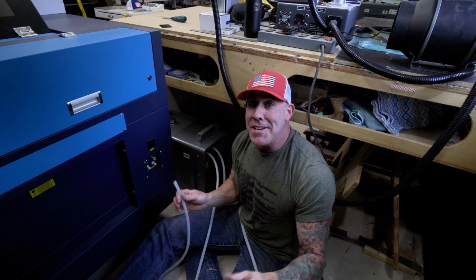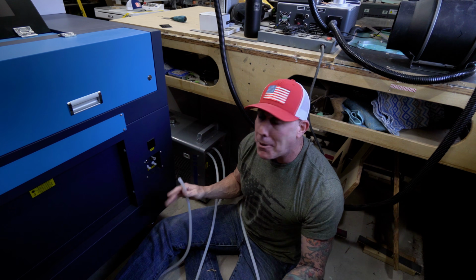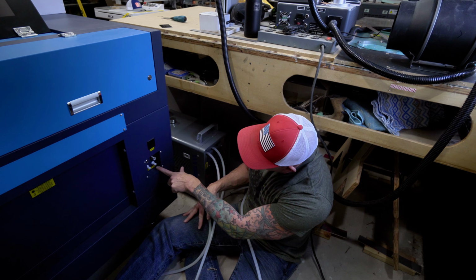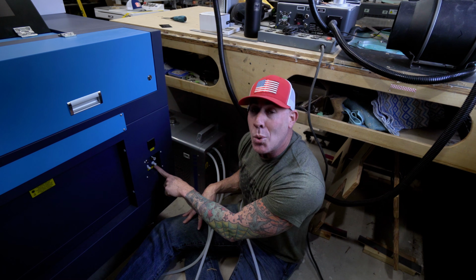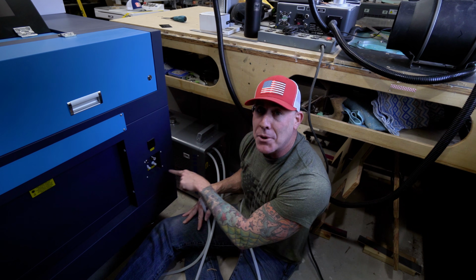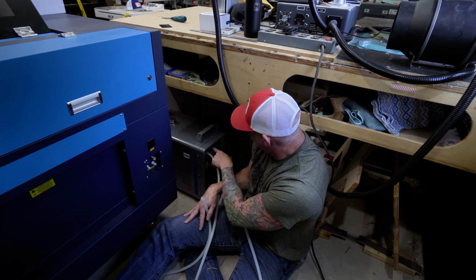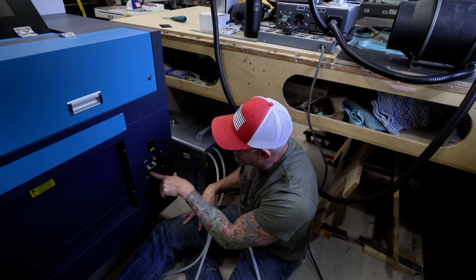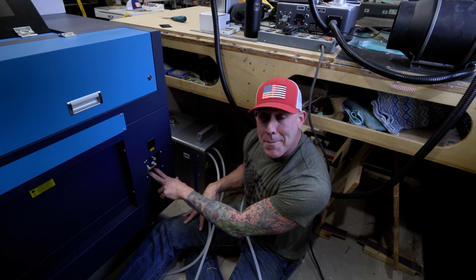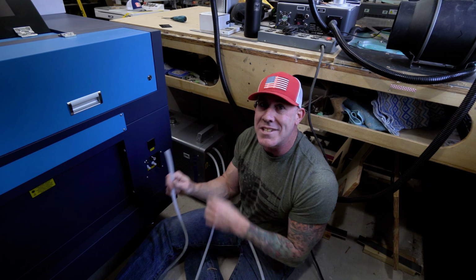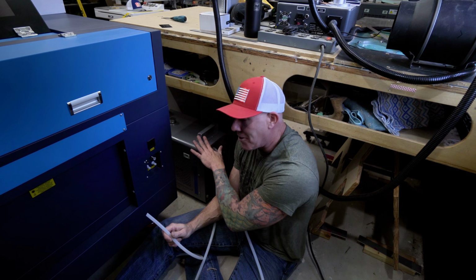Here's where everybody screws this part up. On the back side of the machine, it says water outlet. You want to take the water outlet and connect that to the inlet. Then take the outlet and put that to the inlet. So whatever it says on the back of the machine, just plug the hose into the opposite fitting on the chiller.